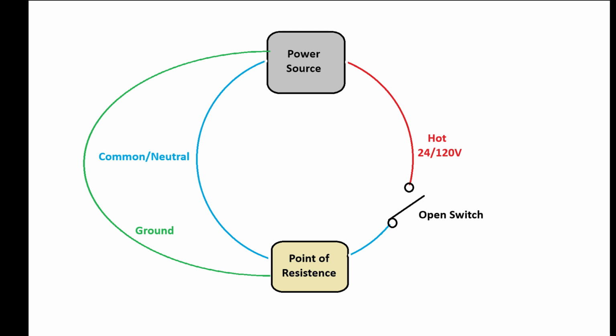Now let's talk a little bit about the ground wire. The ground is an alternate path for power to take in the event there's, say, a short in a circuit. So if there is a bare wire on the hot side rubbing against the chassis of the unit and that unit was properly grounded, we would have a safe path back to our power source. And so that ground wire can be used as a reference point as well, or even the chassis itself, if it's grounded, can be used as a reference point.